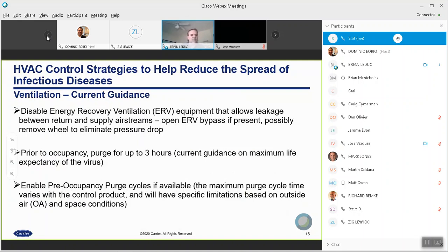They recommend, prior to occupancy, going into a pre-occupancy purge mode for up to 3 hours. Current guidance on the maximum life of the virus is 3 hours, although again, every day there seems to be new information from CDC and World Health about that, but this was what the ASHRAE guidance was based on. Obviously, most of our controls have pre-occupancy purge cycles. The amount of purge that you can implement does vary based on the product.